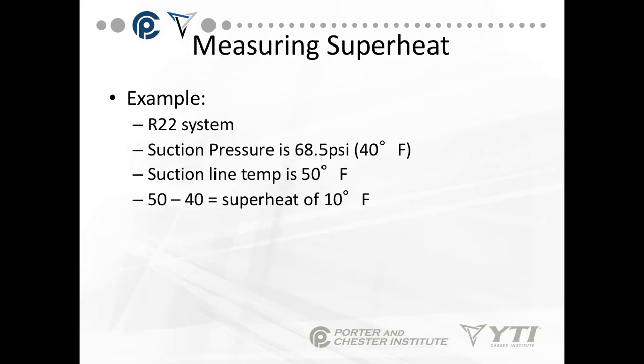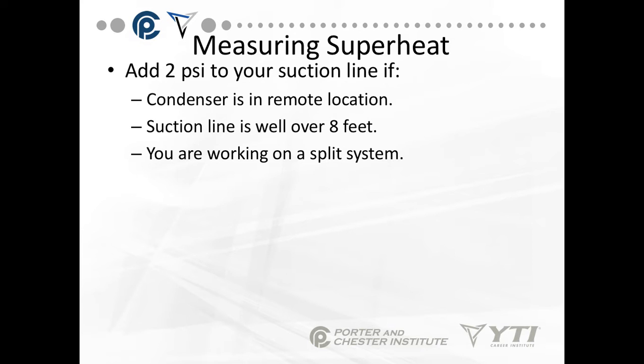For example, on an R22 system, if the suction pressure is 68.5 psi, which is 40 degrees, and the suction line temperature is 50 degrees, then 50 minus 40 gives a superheat of 10 degrees. If your condenser is in a remote location and the suction line is over eight feet and you take your superheat temperatures at the outside unit, add 2 psi to your suction pressures to account for pressure drop before doing your temperature-pressure conversion.